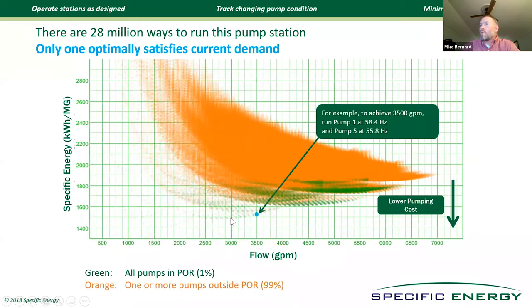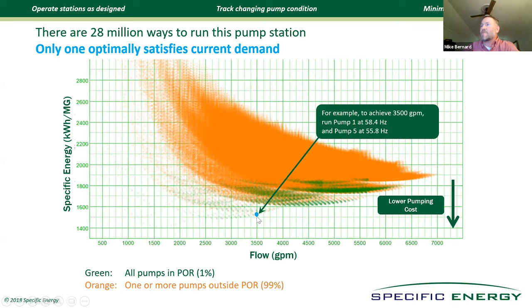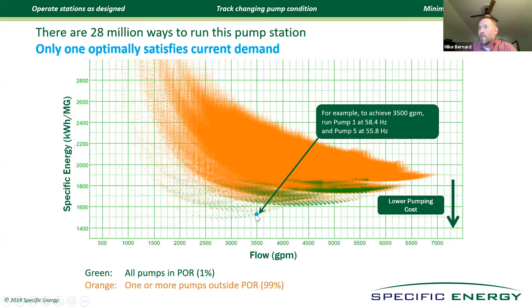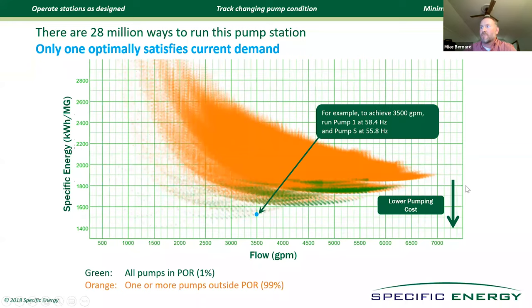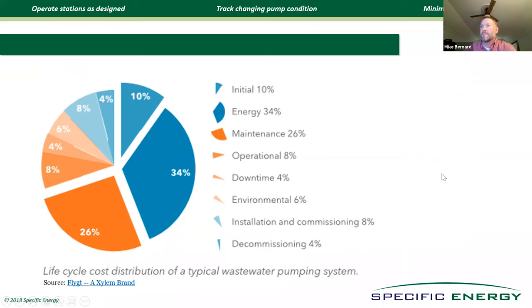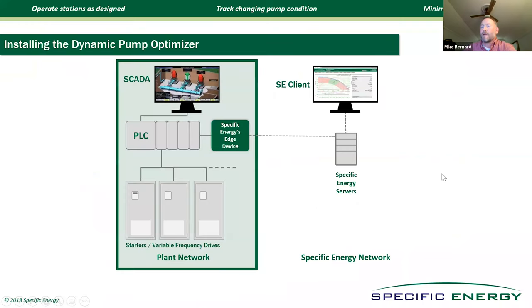But if you put VFDs on those same five pumps and just assume that you can only vary from 60 hertz down to 45 hertz and only at half hertz increments, you just took 32 possible ways to run this pump station and turned it into 28 million possible ways. And unfortunately, of those 28 million ways, 99% of them are bad for at least one of the pumps. What we do is we solve all of these simultaneous nonlinear equations in real time and can tell you at any given flow rate the perfect combination of pumps and speeds. This is going to be at the point of minimum specific energy, which means you're going to save energy expenditure, and these pumps are going to last longer.